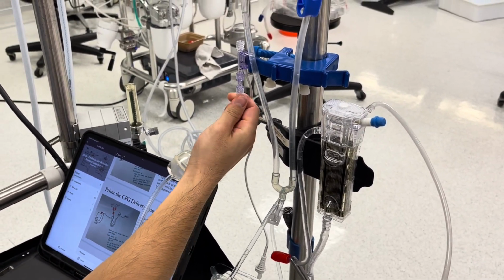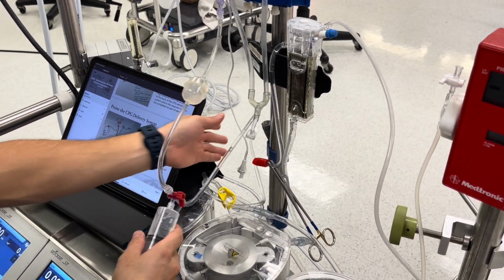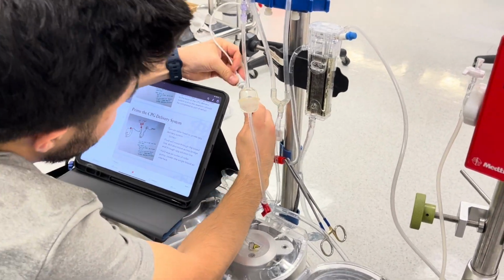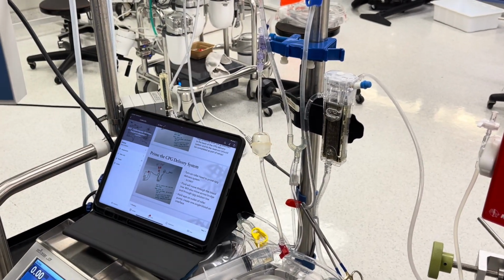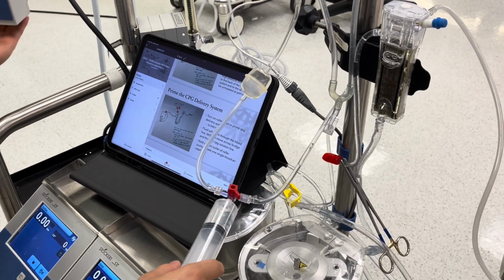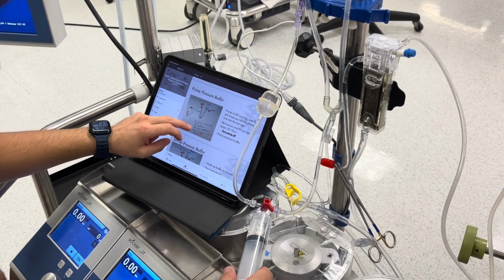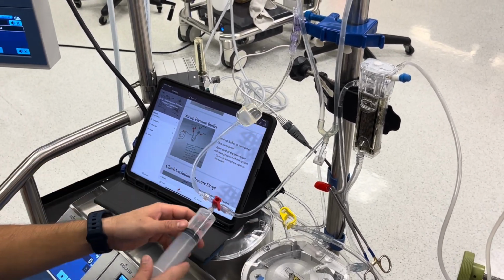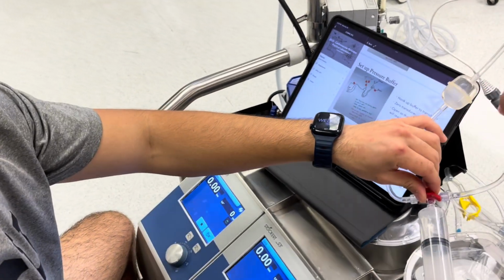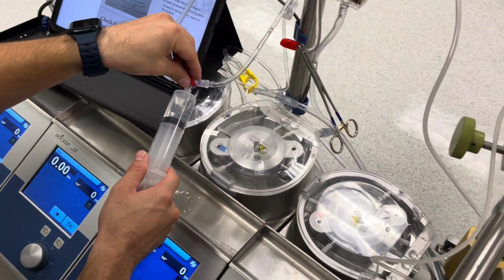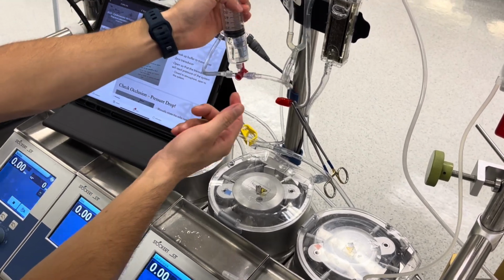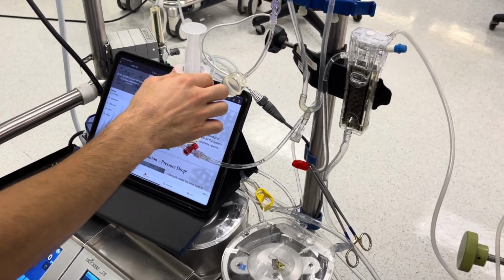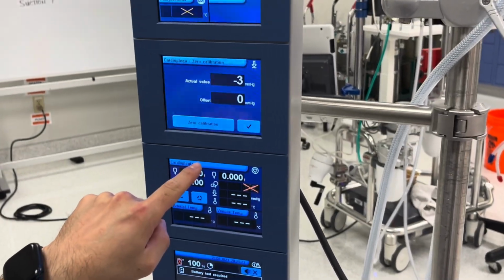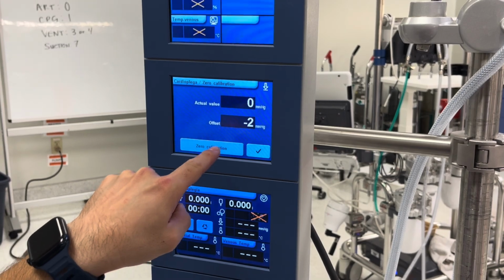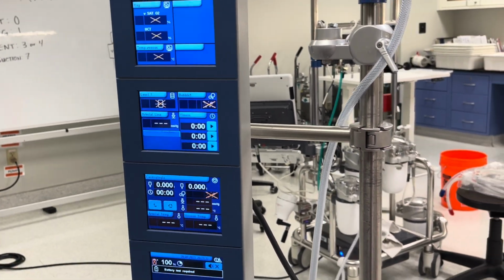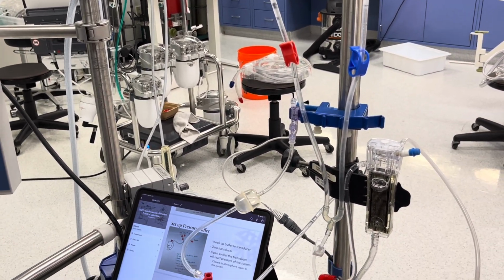and then you connect it to your transducer, and this should be connected here. We probably should have done that earlier. Connect the connection here, make sure it's screwed on, and then it should display here, right? Hook up buffer to transducer, zero to transducer. So then you would open it to just this line. This one? Yeah, just straight through here. Okay. So you go off to the stopcock, or the syringe, and then you go over here to Cardioplegia and do zero calibration. So now it goes to zero, which you want. Boom. And now it's good to transduce.